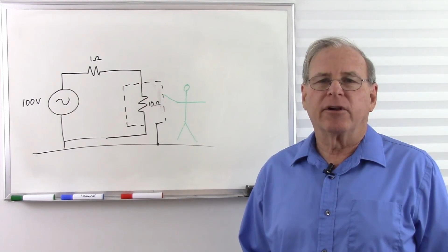You put one probe at one voltage, and you put the other probe at another voltage, and it tells you the difference in voltage between the two. If you put the red probe at the higher voltage, it'll tell you a positive voltage, and if you put the black probe at the higher voltage, it'll give you a negative voltage. When a voltmeter reads 0, all it's telling you is that the red probe and the black probe are at the same voltage. So wherever we put our black probe, that by definition is 0 volts. Our red probe will then tell us if the voltage at the red probe is higher, lower, or the same.